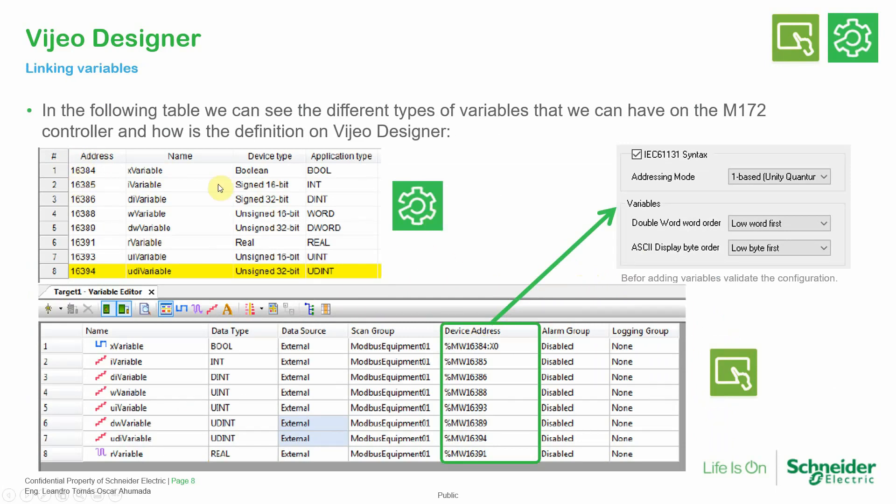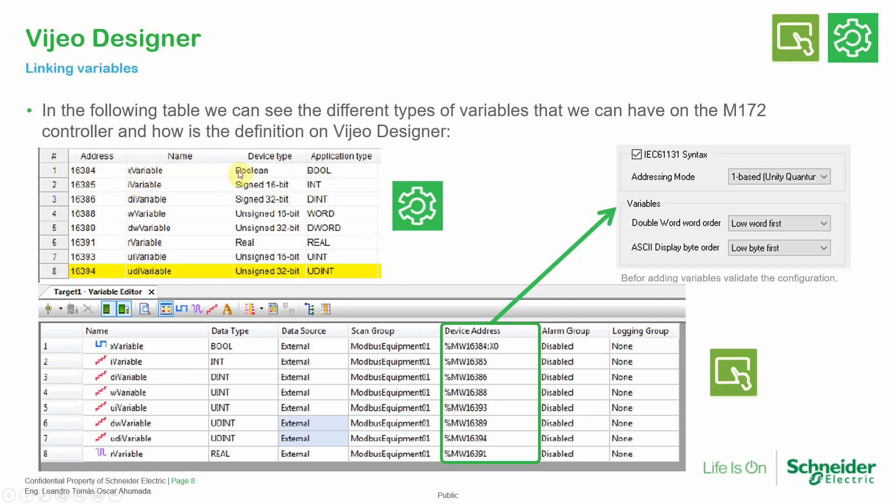For example, in this particular example, these are the variables on the PLC and then the M172 where I have this information. In this example you can see how you can address those different types of variables of the PLC. For example, we have a boolean, and then we access the boolean like this. We need to put the memory address for the word and then the bit. And it's the same for the rest of the variables. Instead of the bit, we just leave the word in there, simple as that. We just need to copy the variable address %MW and that's it. It only changes for the boolean where I need to specify the bit.